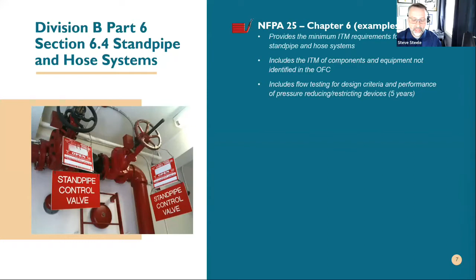and verified as well. Most importantly, especially when you look at standpipe systems and the need and the use of these for firefighting provisions, beyond everything, and I know we're going through hoses, what's going to be there, testing of hoses, are they actually being used? Irrelevant to that, the most important part is the valve and the exercise and use of that valve. And there are cases, especially in high pressure, when a valve's been closed and sitting closed for 5 years, 10 years, 15 years, there have been cases of failure to open and operate, and if you're not exercising or doing a proper full function test of these systems, you have no way of ensuring or knowing that these things are going to work.